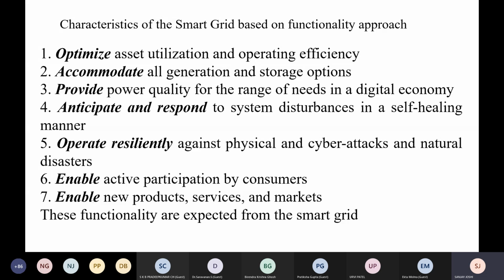Self-healing means if there is a faulty part in a distribution or transmission network, it should separate from the grid, and supply to the consumers should be restored. That doesn't mean that when a fault occurs, the smart grid will take actions such that the fault itself is removed from the transformer or feeder and it is self-healed. No, that is not the point.